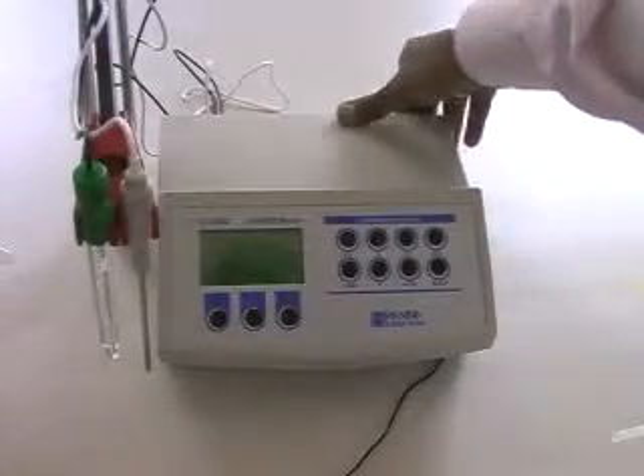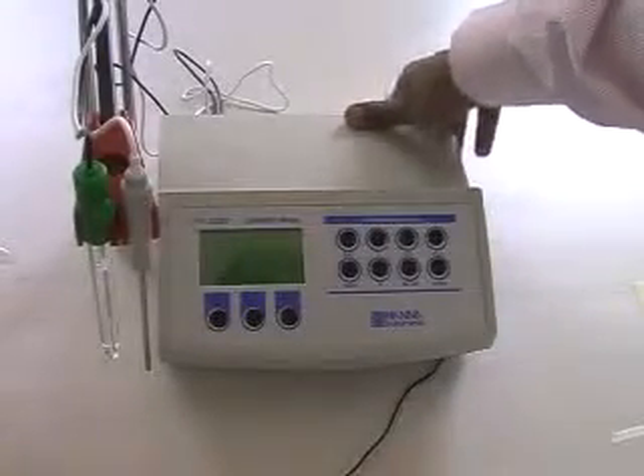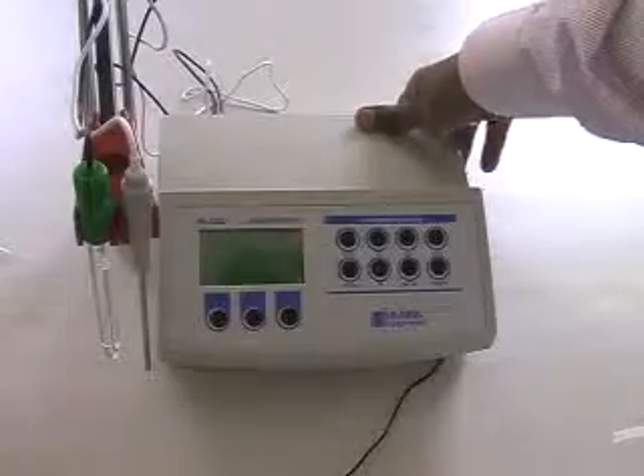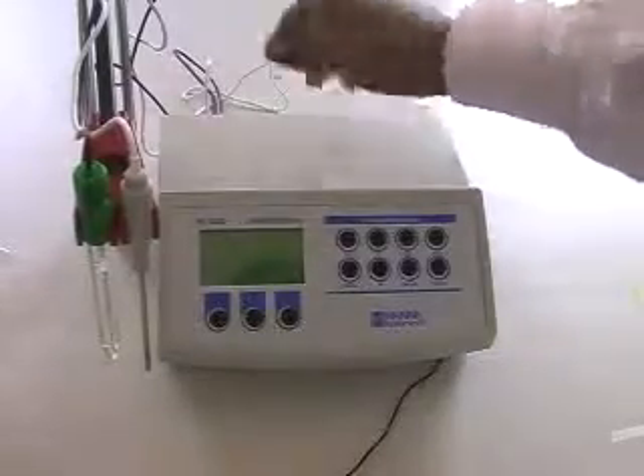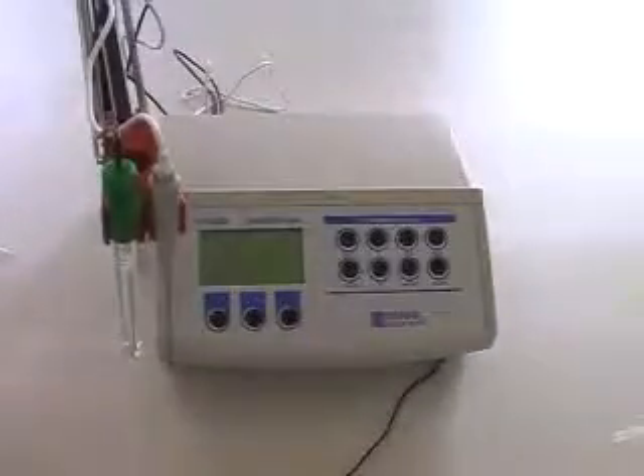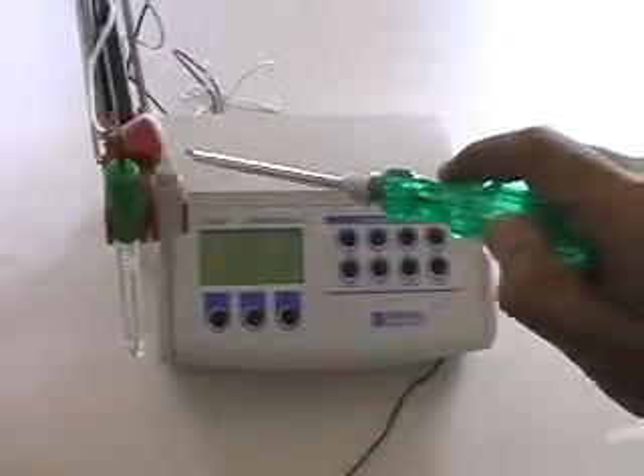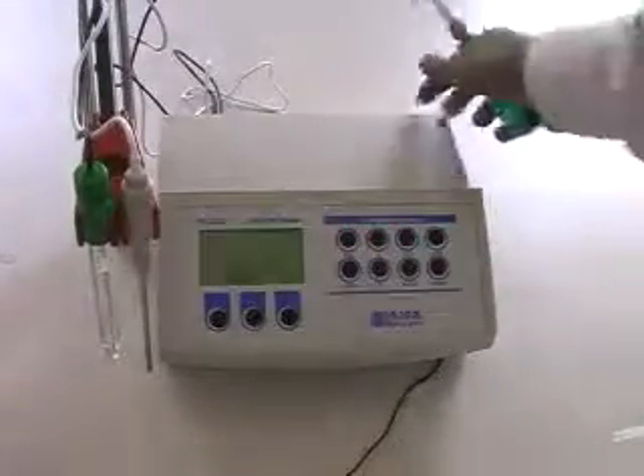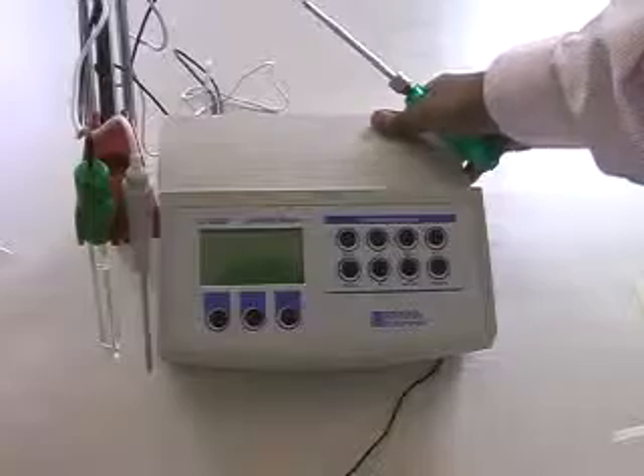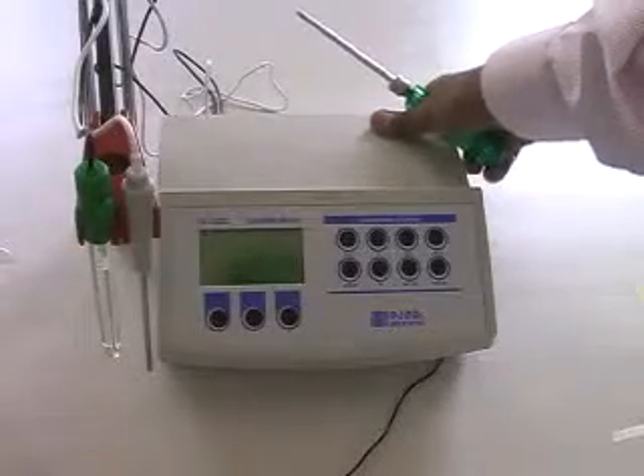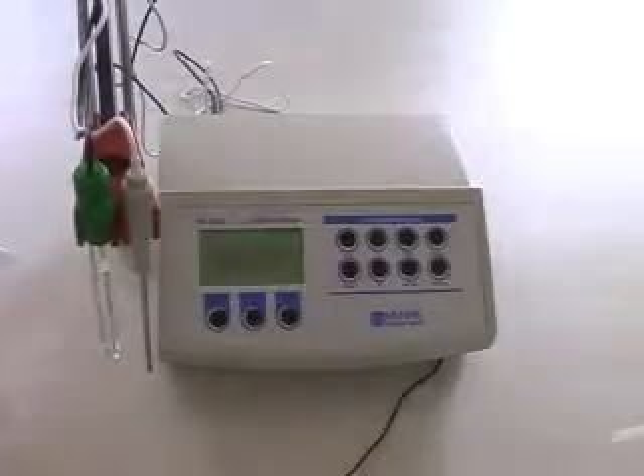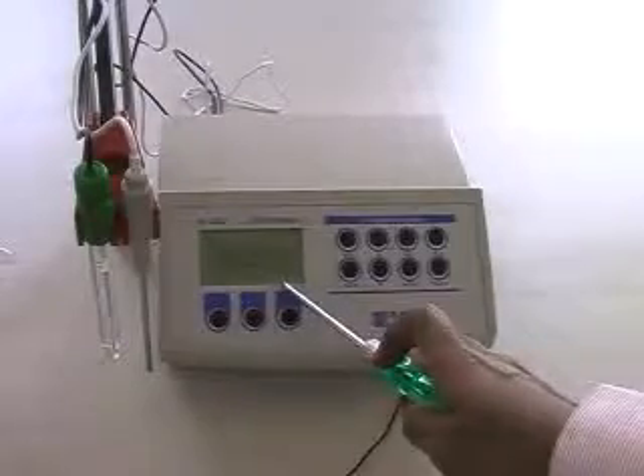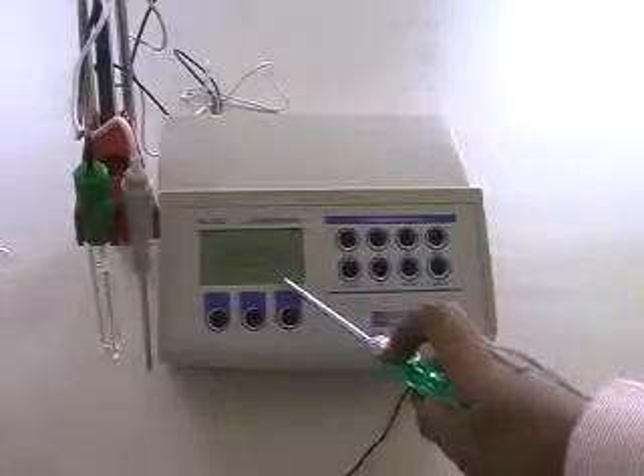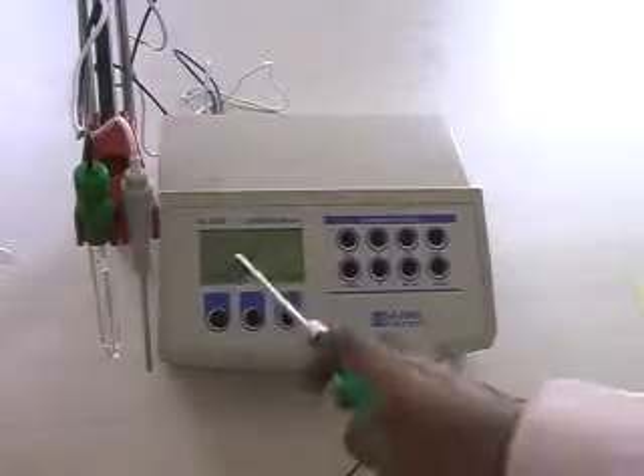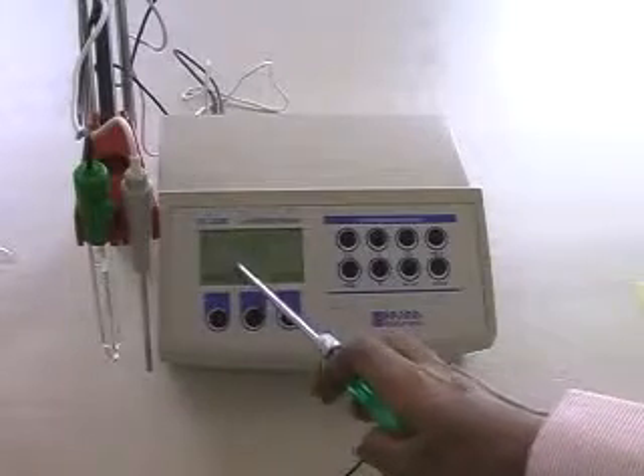Just before you switch on the instrument, make sure that all the accessories are connected properly to the meter, like the pH electrode, then the temperature probe, then the 12 volt DC adapter. Just switch on your instrument. It will show the Hanna Instruments logo, then loading log. If there is something in the log, then it will directly show the normal measurement mode.